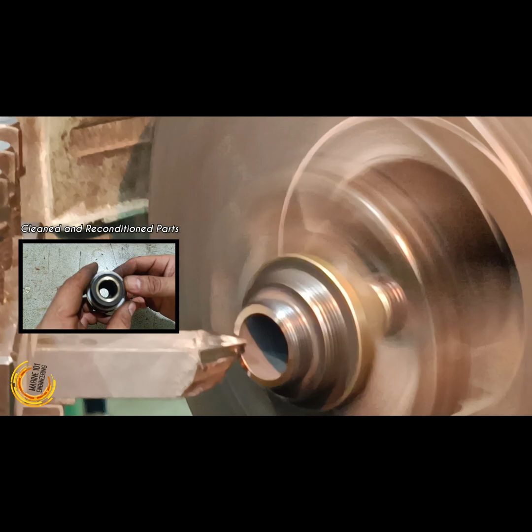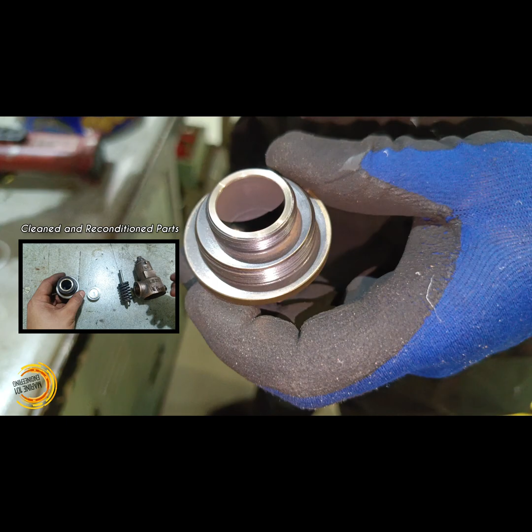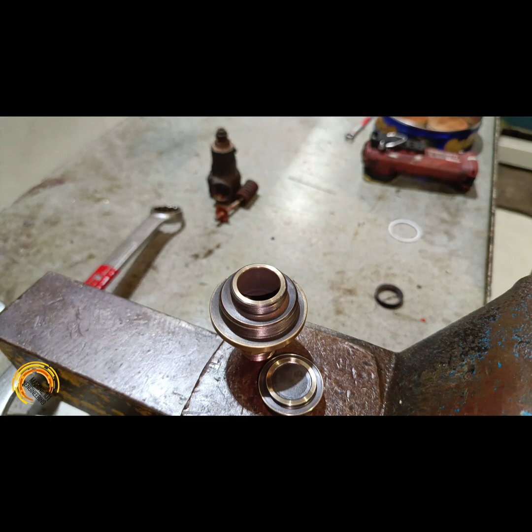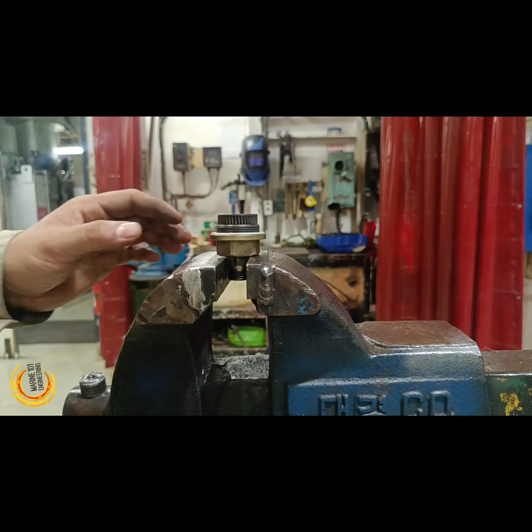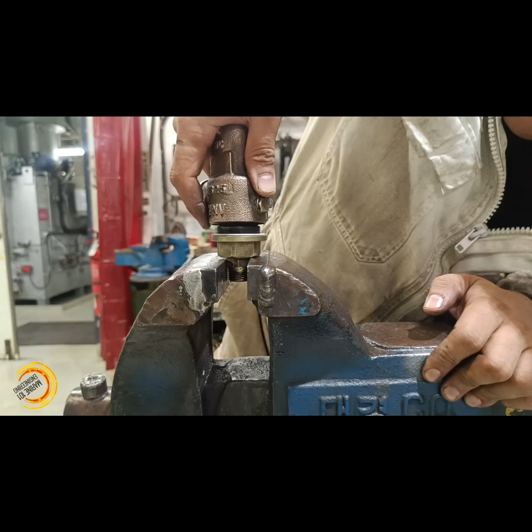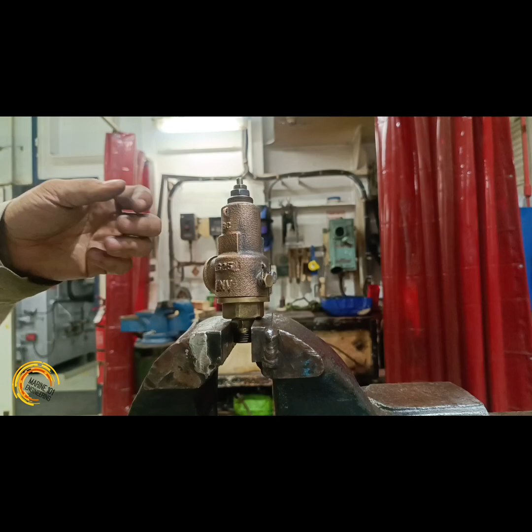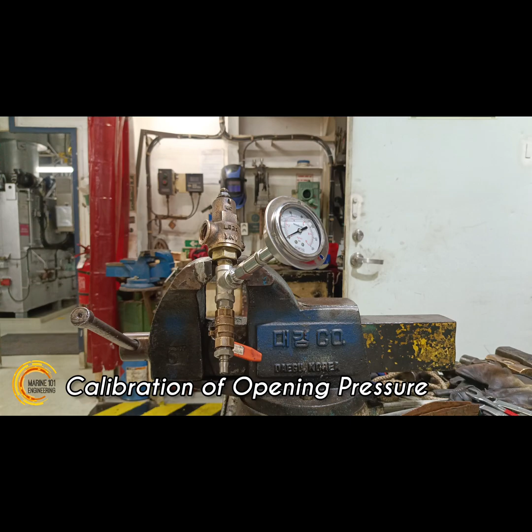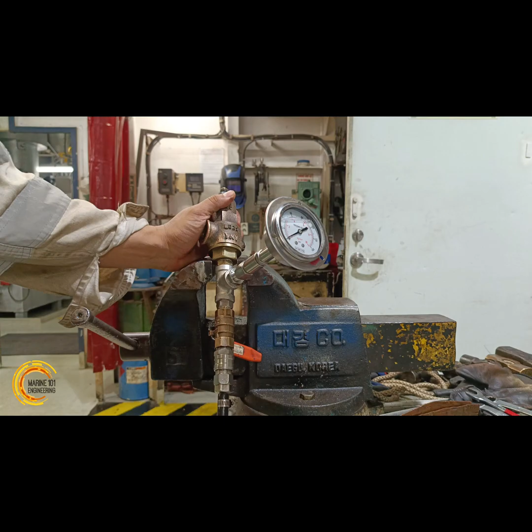After careful inspection and all parts fully clean, the valve is ready to be assembled. The assembly of the valve requires proper order and adjustment of spindle height. In the absence of a pressure calibrator, we used a simple T connection with pressure gauge to record opening pressure adjustments. The adjustment of spindle height corresponds to set point on opening pressure.